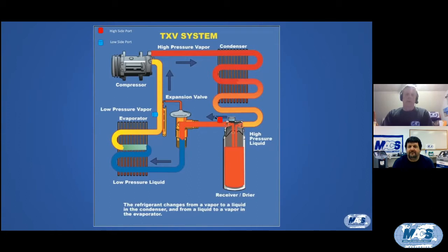If the service port was located at the compressor, we would be able to see what the true high side pressure was there at the compressor. So let's transition into my service port wish list here. With regard to my service port wish list, let's do some counting.